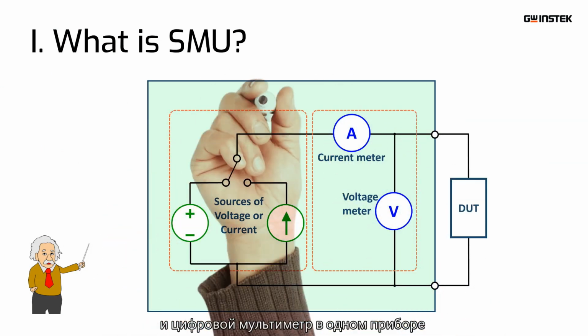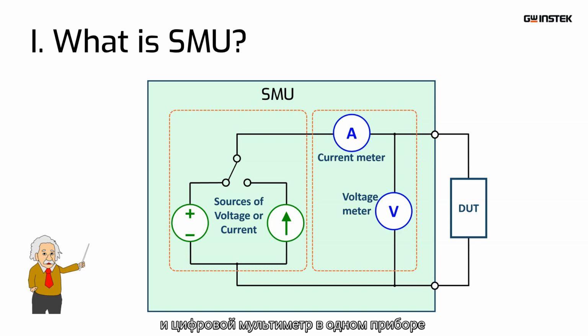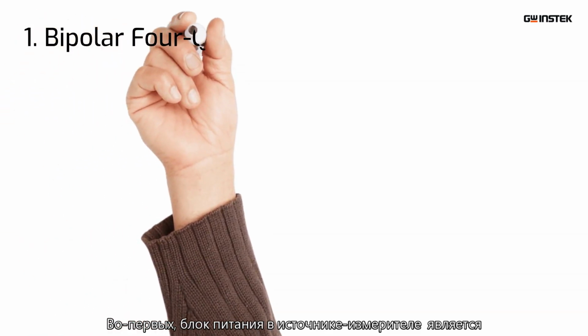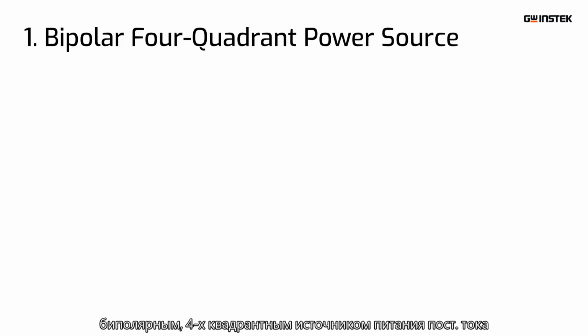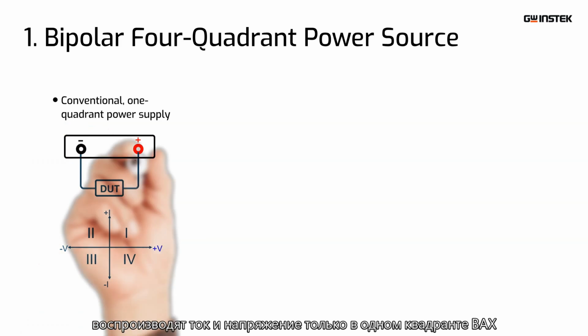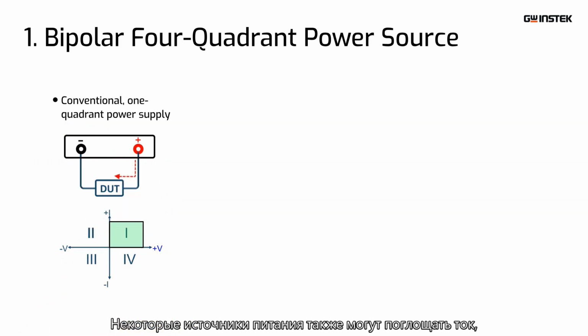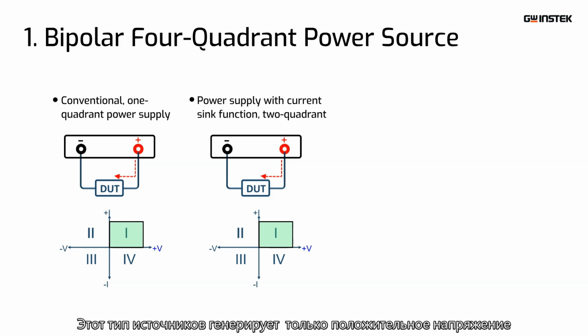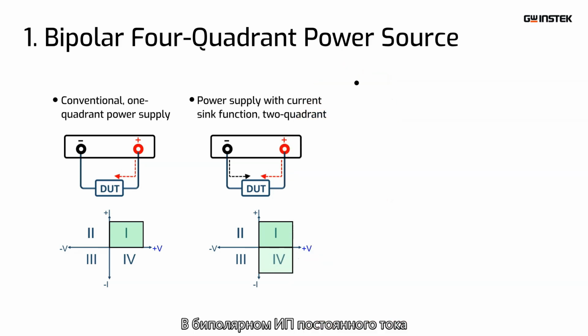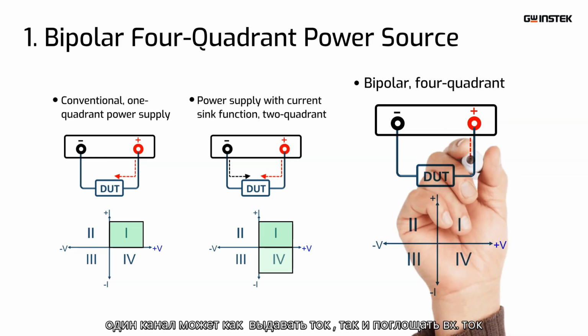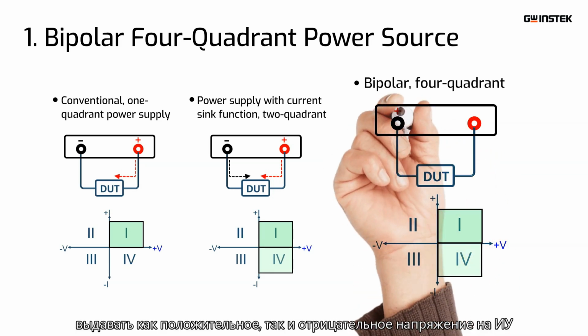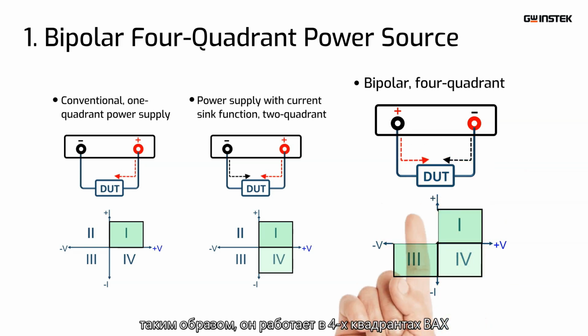What is an SMU? An SMU combines the DC power source and digital multimeter into one box. Firstly, the DC power source in the SMU is a bipolar, four-quadrant power supply. Conventional DC power supplies only generate voltage and current in quadrant 1. Some power supplies can also sink current like a load. For this type, only positive voltage is supplied, therefore it is a two-quadrant source. For the bipolar DC power source, a single channel can output and sink current, and supply both positive and negative voltage to the DUT, so it works in four quadrants.